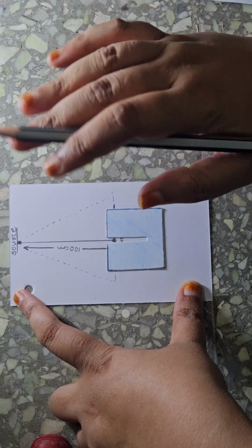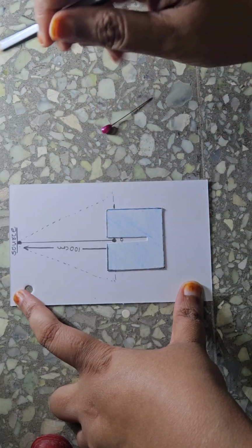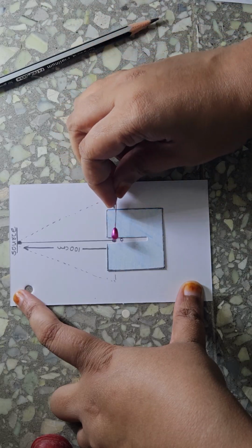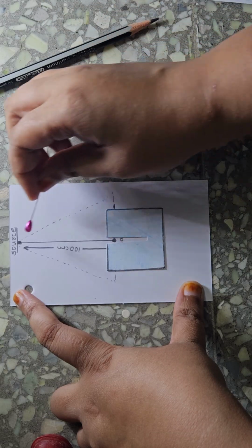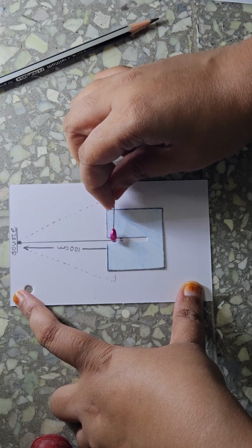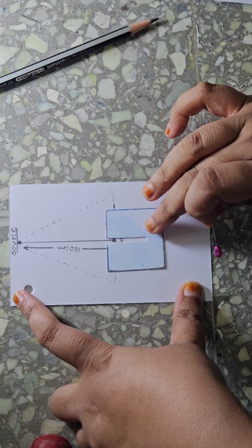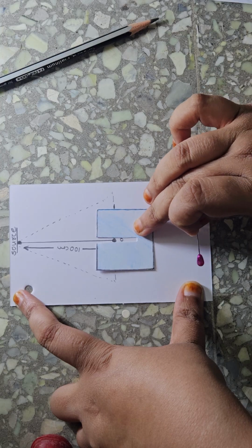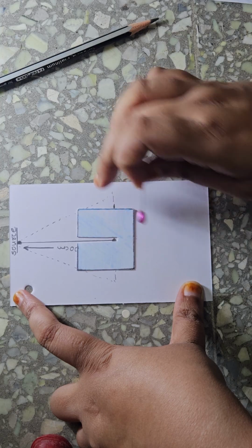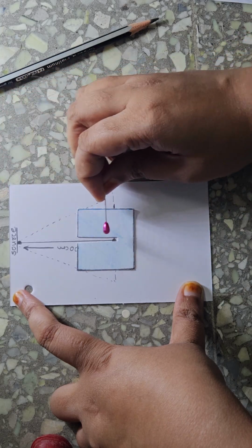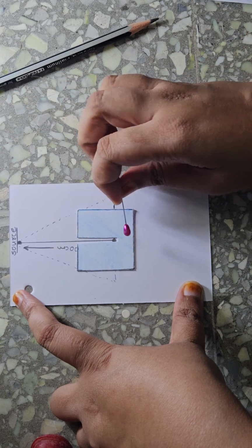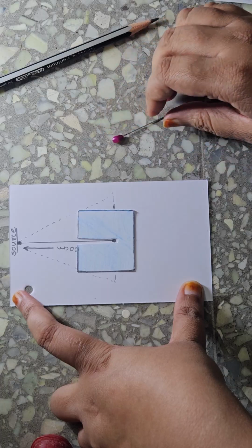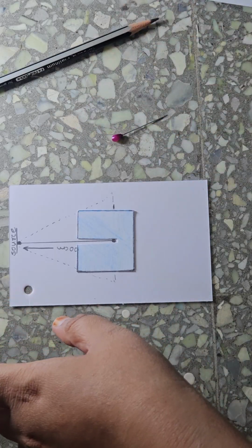The SSD technique is no more there. Now it is SAD technique. Now I'll measure the dose here at the Dmax. Now in SAD technique, I'm measuring the dose at the Dmax. Now I'll move the phantom. In the previous case, I didn't move the phantom. In this case, I'll move the phantom here. So the SSD is moved closer, and now I'm measuring the dose over here at a depth D. So that ratio will be TMR.